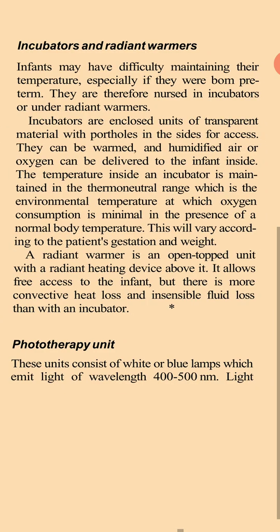Incubators and radiant warmers. Infants may have difficulty maintaining their temperature, especially if they were born preterm. They are therefore nursed in incubators or under radiant warmers. Incubators are closed units of transparent material with portholes in the sides for access. They can be warmed and humidified. Air or oxygen can be delivered to the infant inside. The temperature inside an incubator is maintained in the thermo-neutral range, which is the environmental temperature at which oxygen consumption is minimal in the presence of a normal body temperature. This will vary according to the patient's gestation and weight.